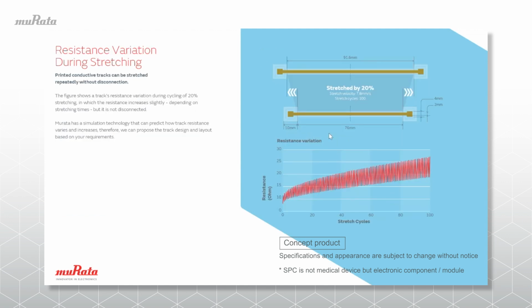The beauty of a stretchable printed circuit is that electrical performance is maintained even if the electrodes are stretched. However, this does bring the challenge that when stretched, the resistance of the tracks changes. And you can see the typical change of resistance increase over 100 cycles of 20% stretching in this data on the right-hand side. Murata has a lot of experience and tools to simulate the stretching effect to create the optimal layout, for example, the direction, width, and thickness of the tracks.